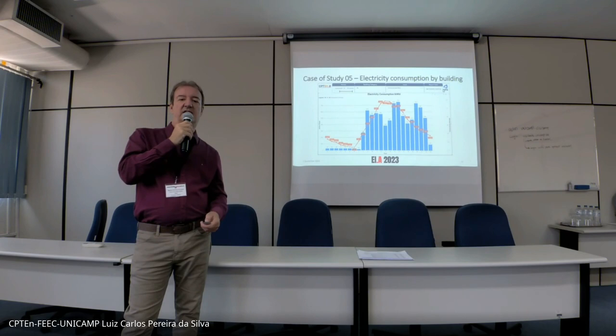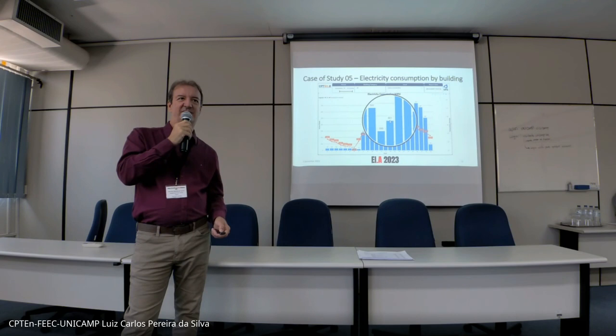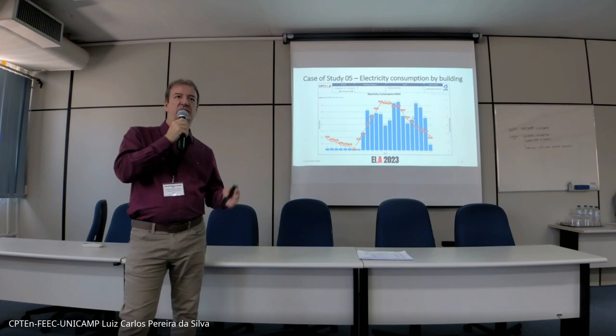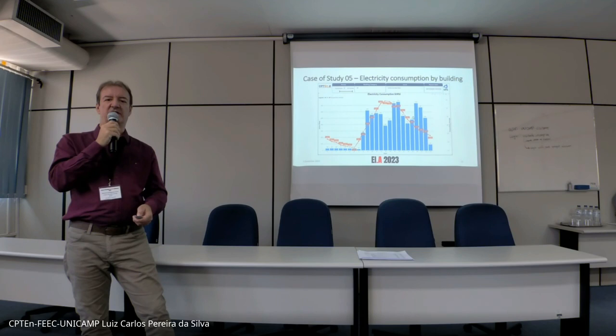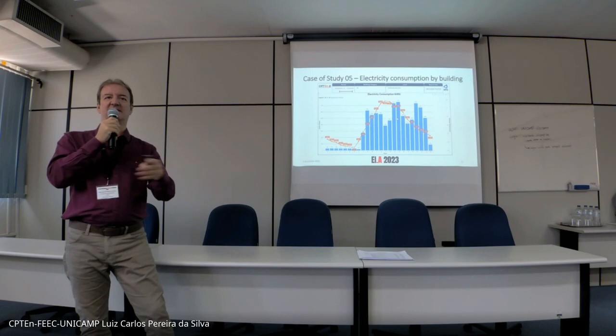And then, to finish, you can cross-relate it with temperature. As the temperature rises, the consumption of energy rises. And during the interval of classes, it reduces, and so on. So you have a load of electricity during the day, and you can take an approach to automatically take off all the air conditioners during the period of interval. It's a cut of demand. You can control demand if you monitor it.